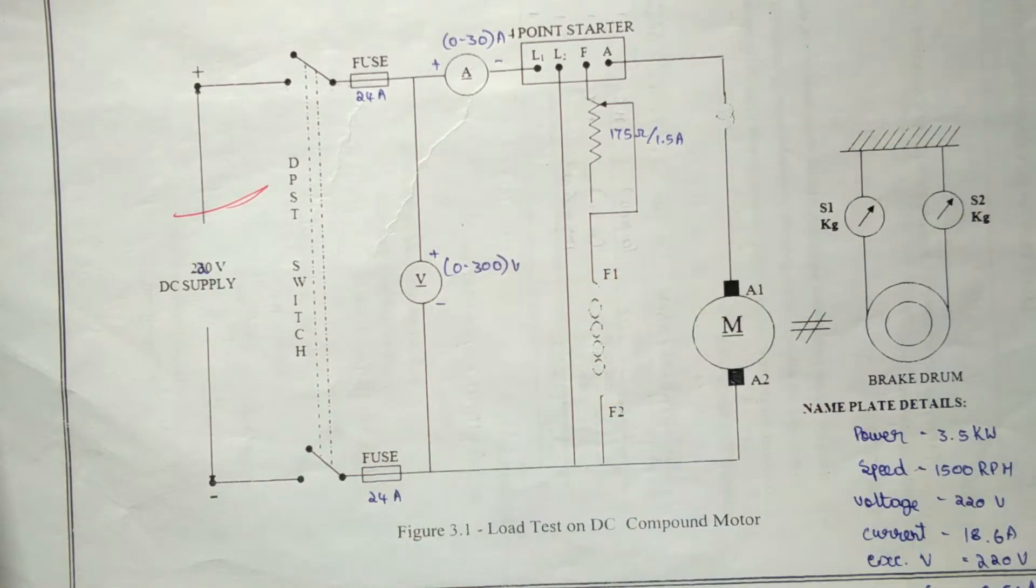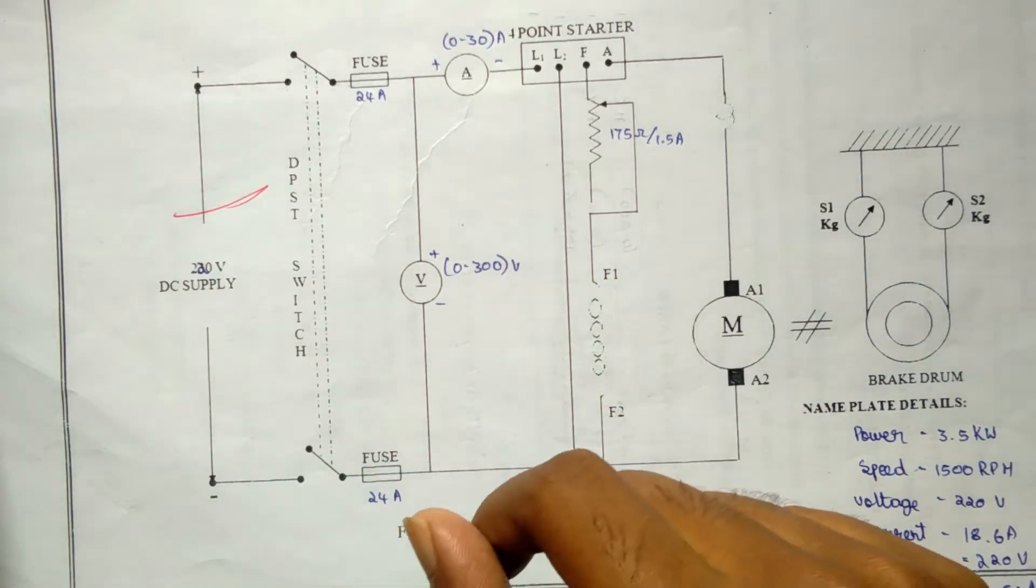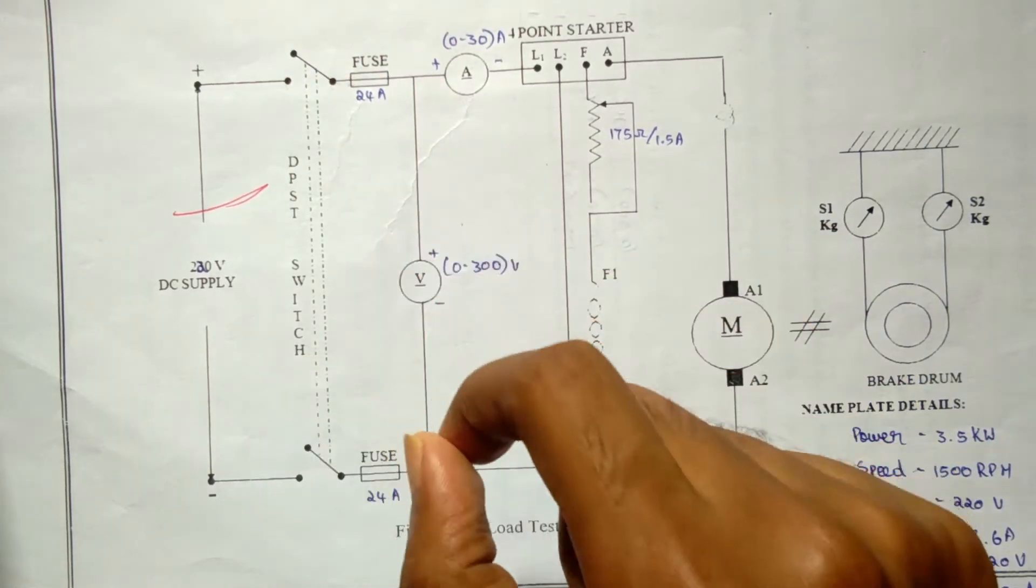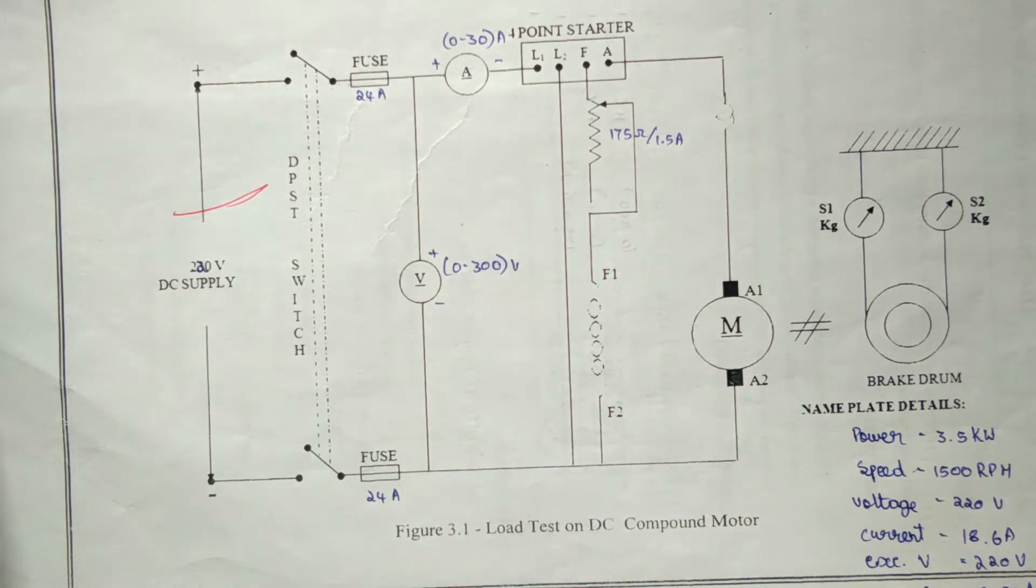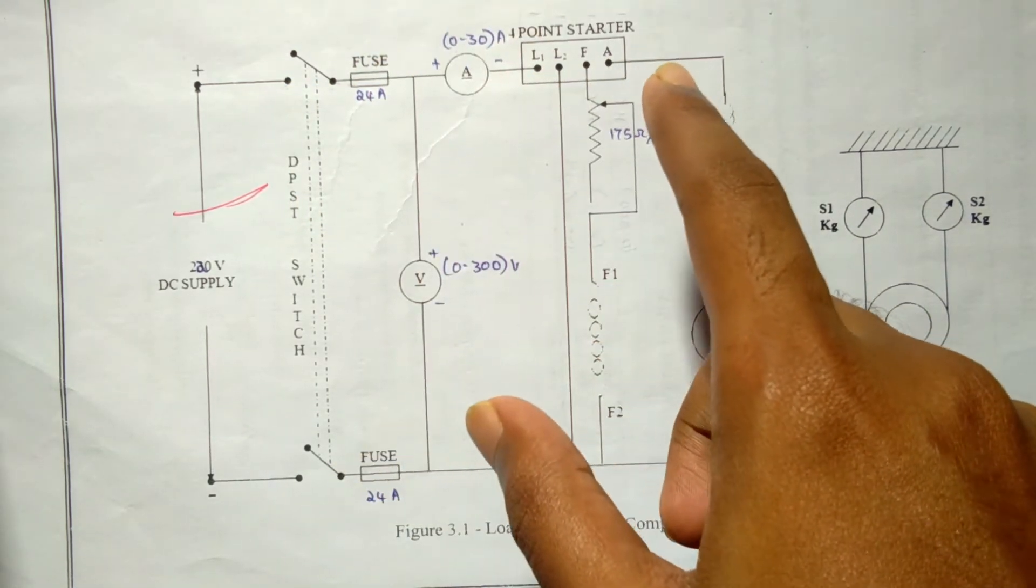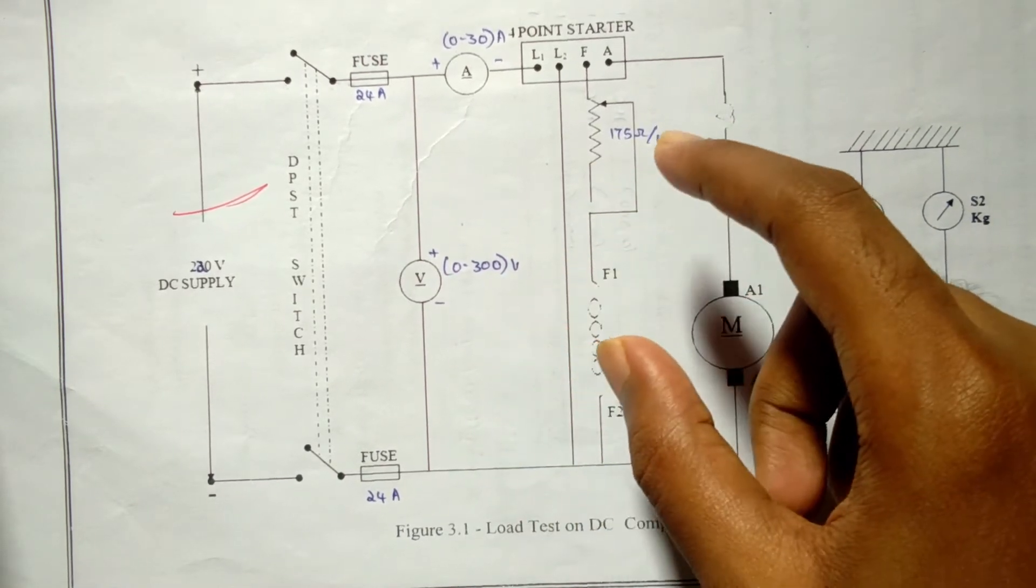Before going to the procedure, we should follow the precautions. The fuse is selected such that its rating is 120% of the rated current. It is ensured that the starter is in the off position.